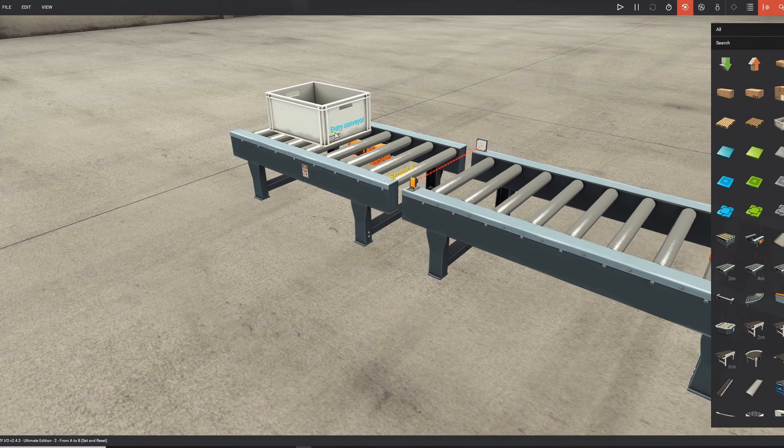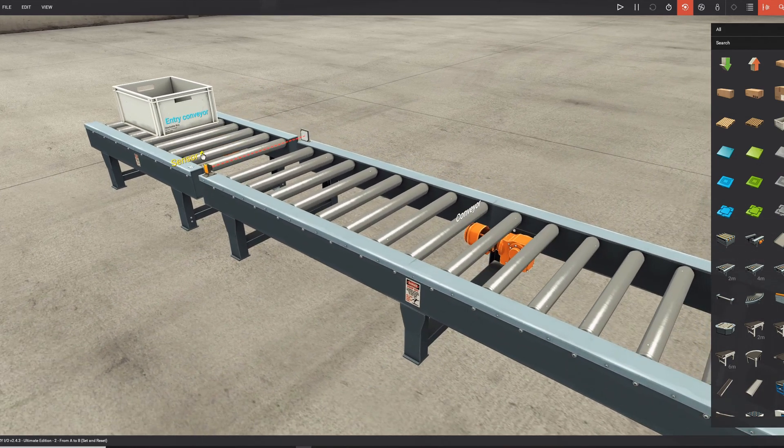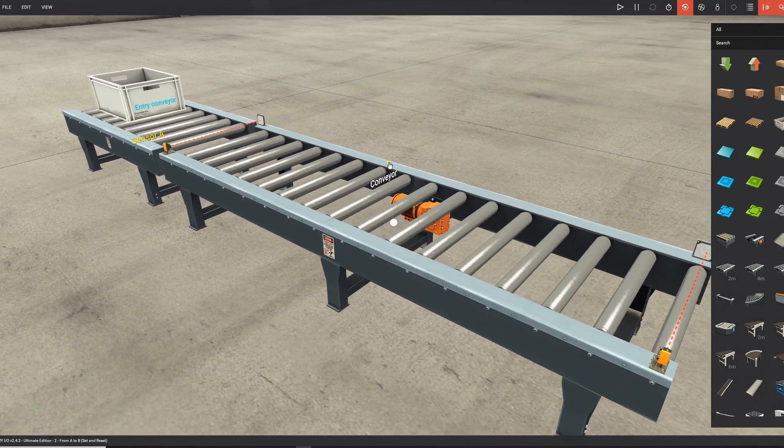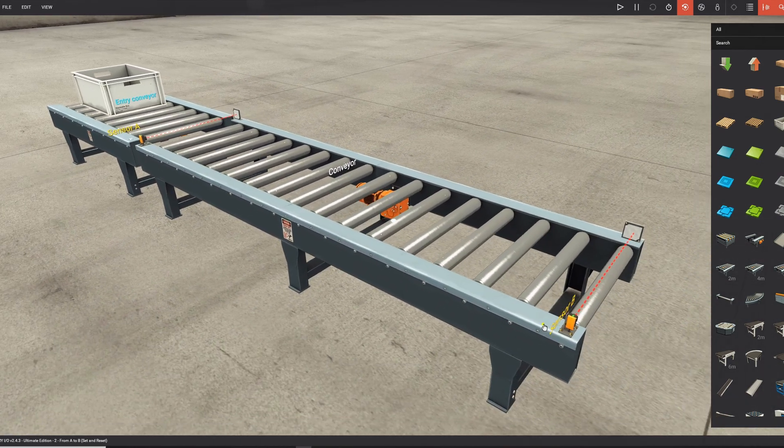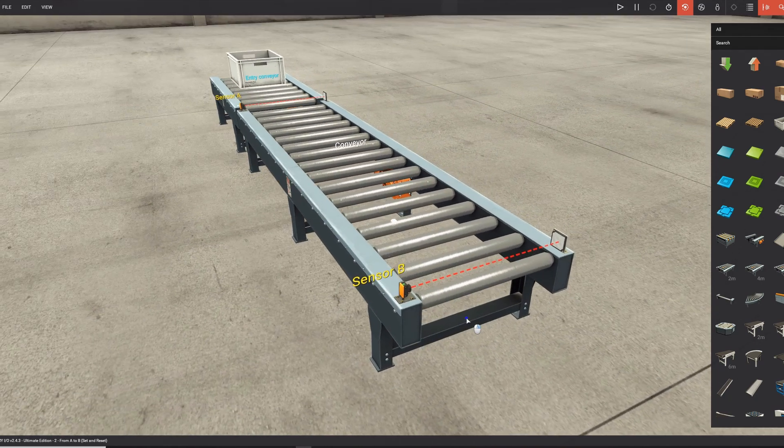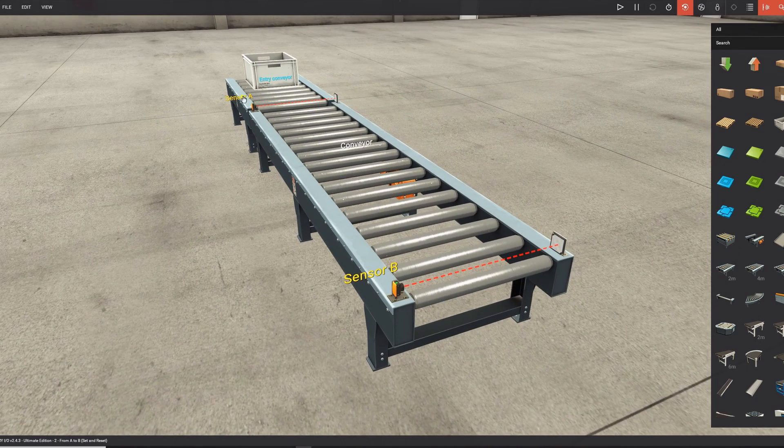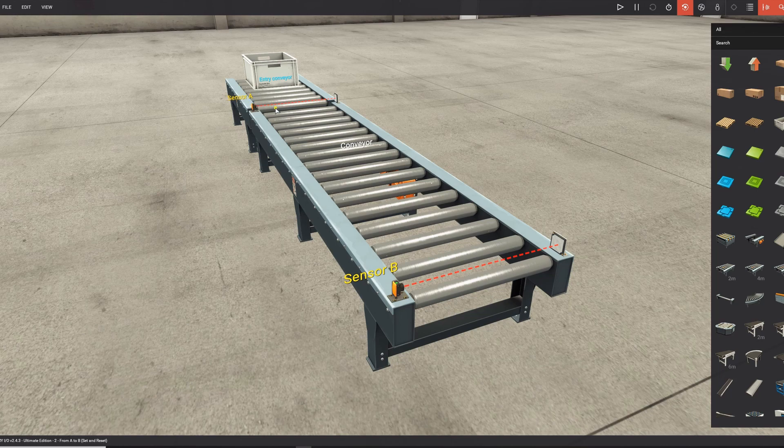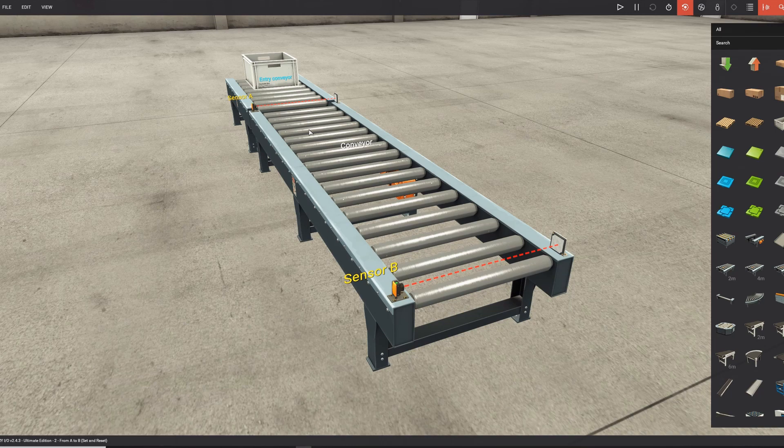So you have this entry conveyor, you have a sensor A, a conveyor, and a sensor B. You can see sensor A is yellow, this is because it's true now. And that's because it sees the reflector. So it's true when there is no box in front of it, and false when there is a box in front of it. And it's important that you know that for writing your logic.